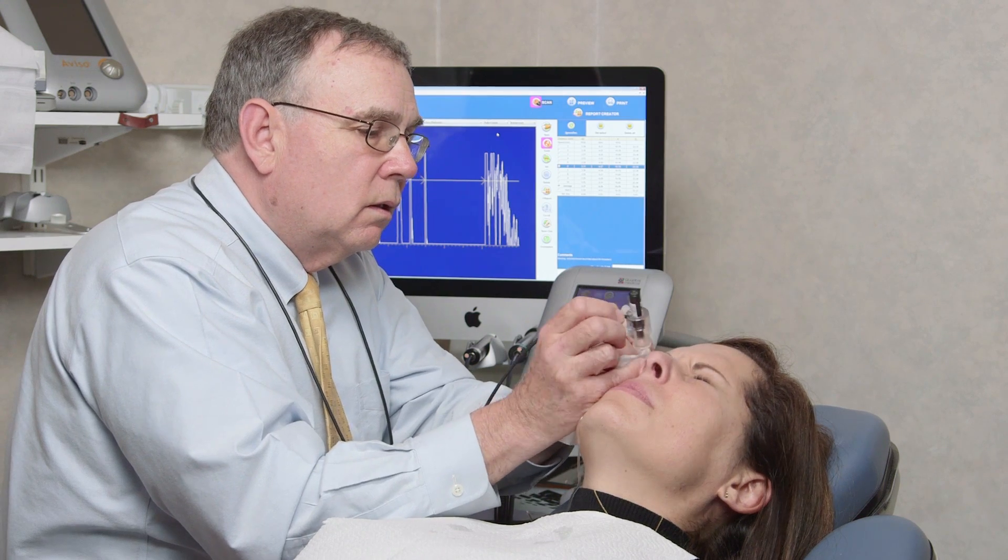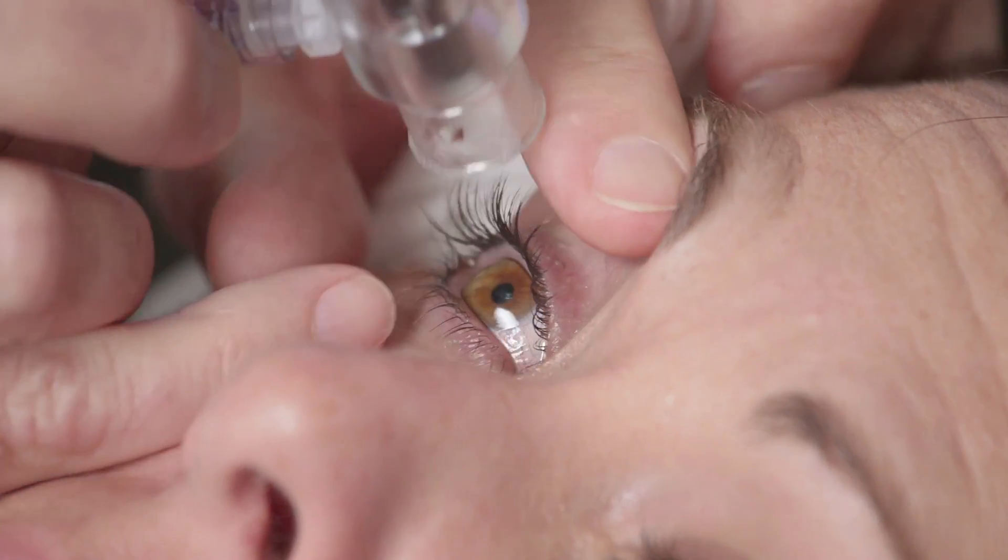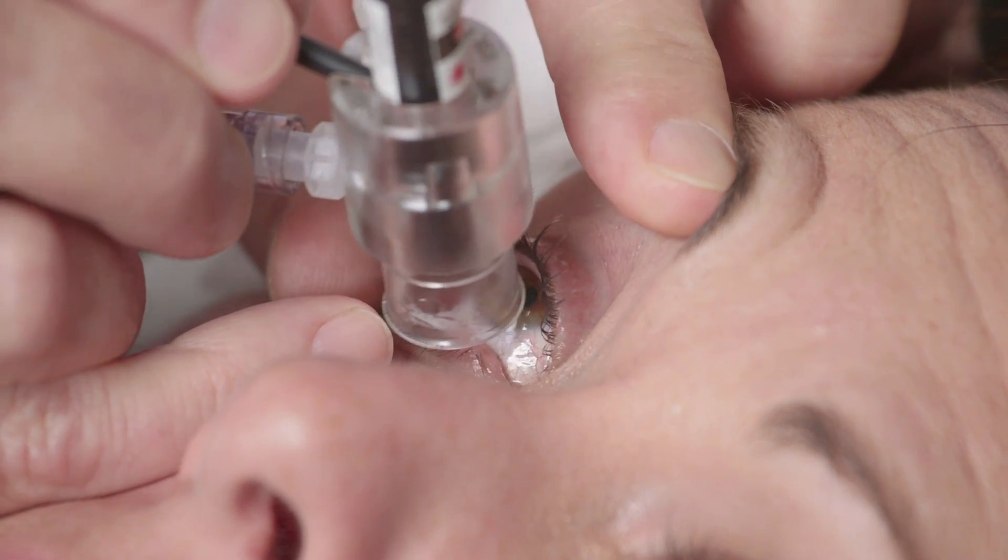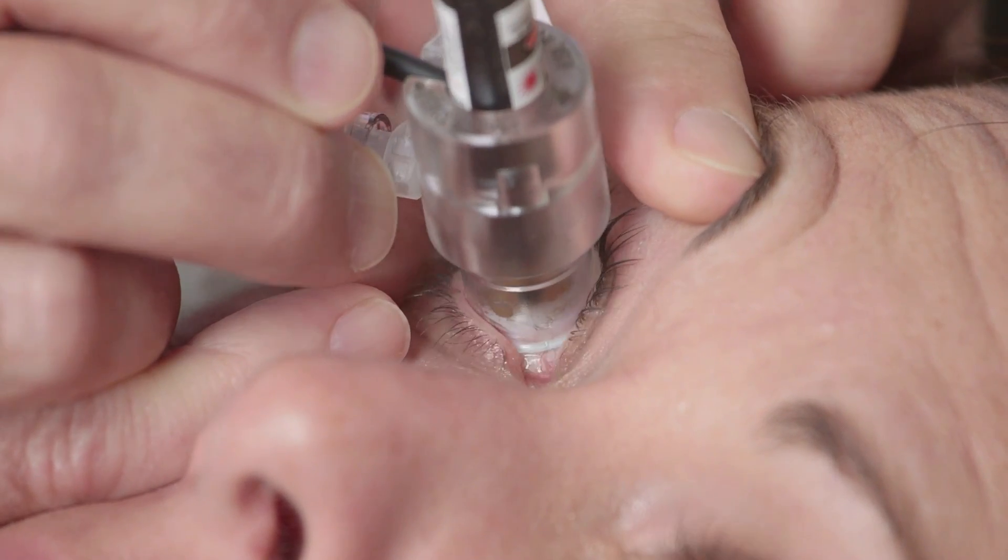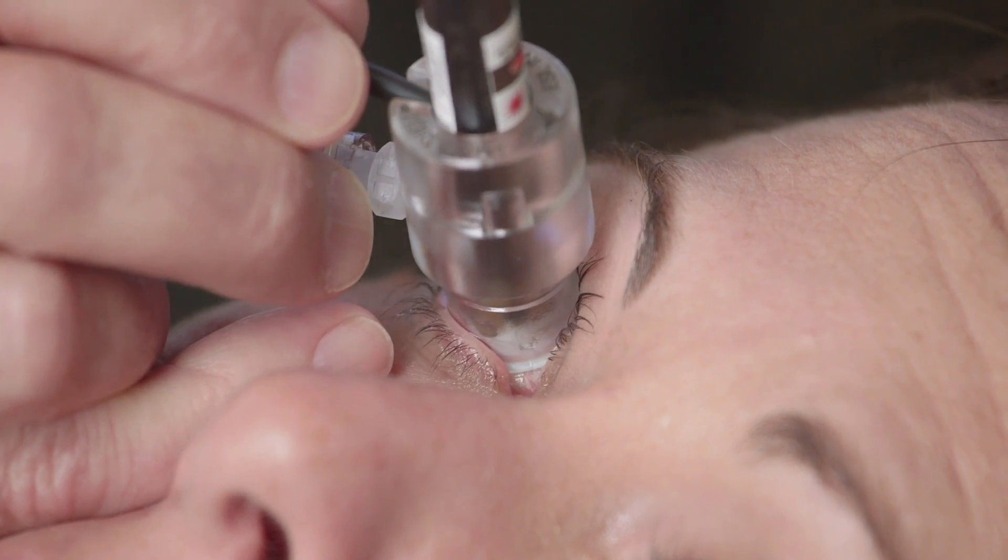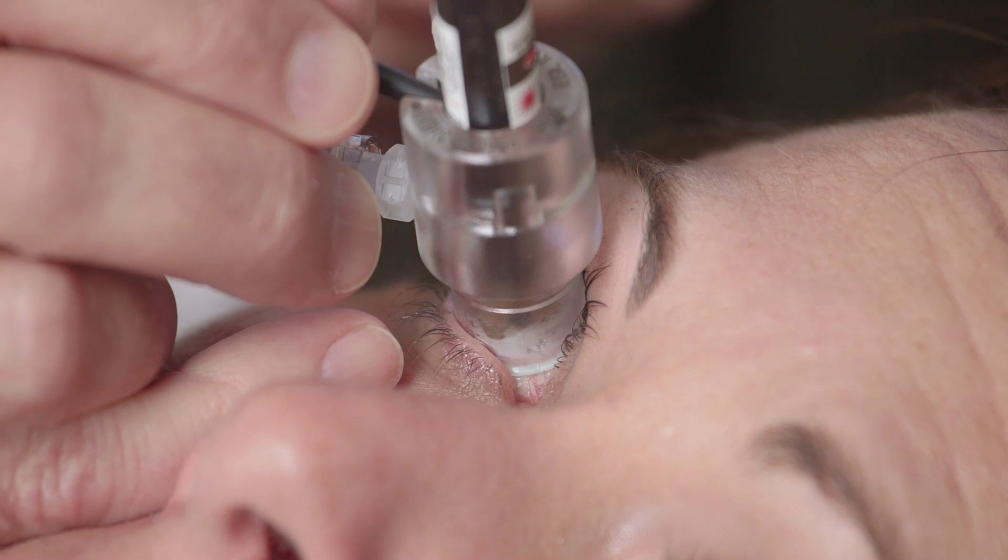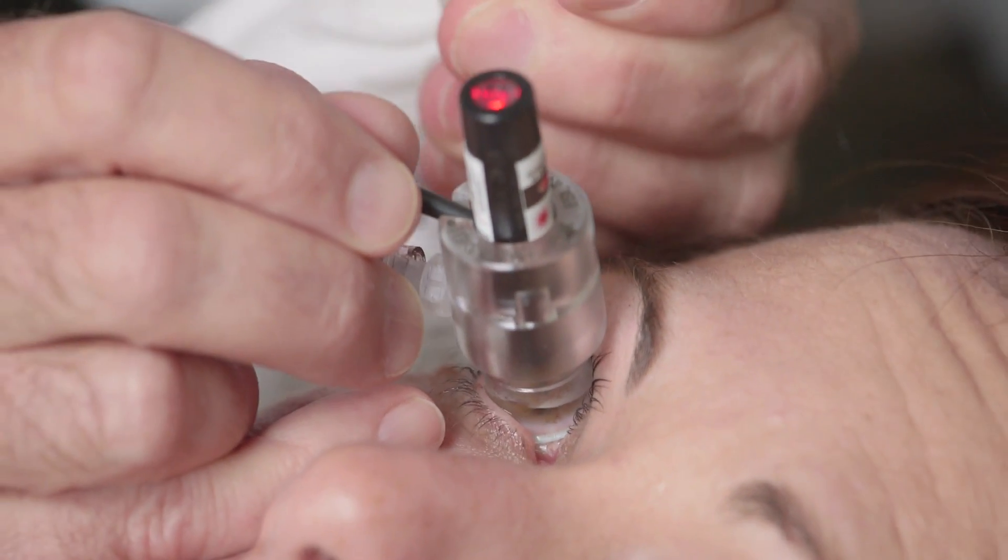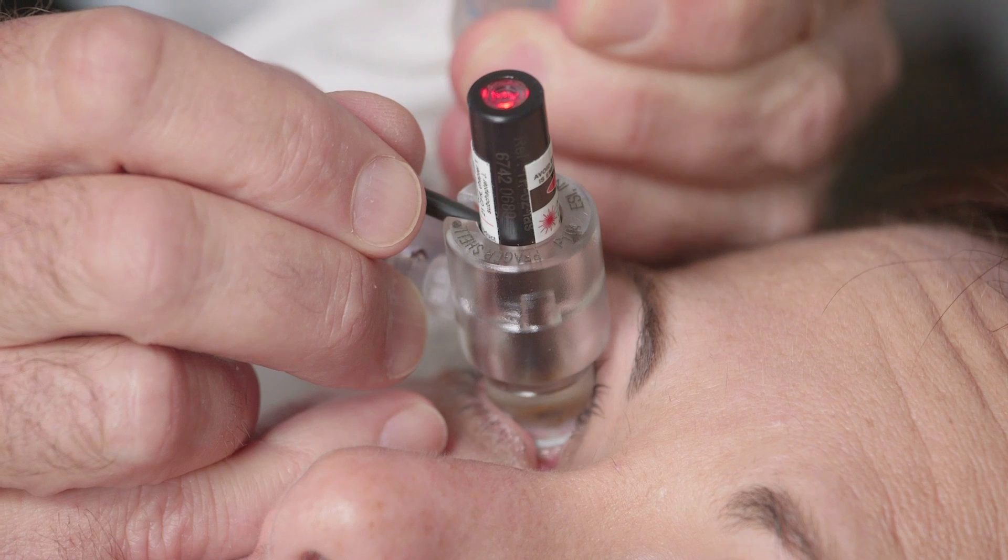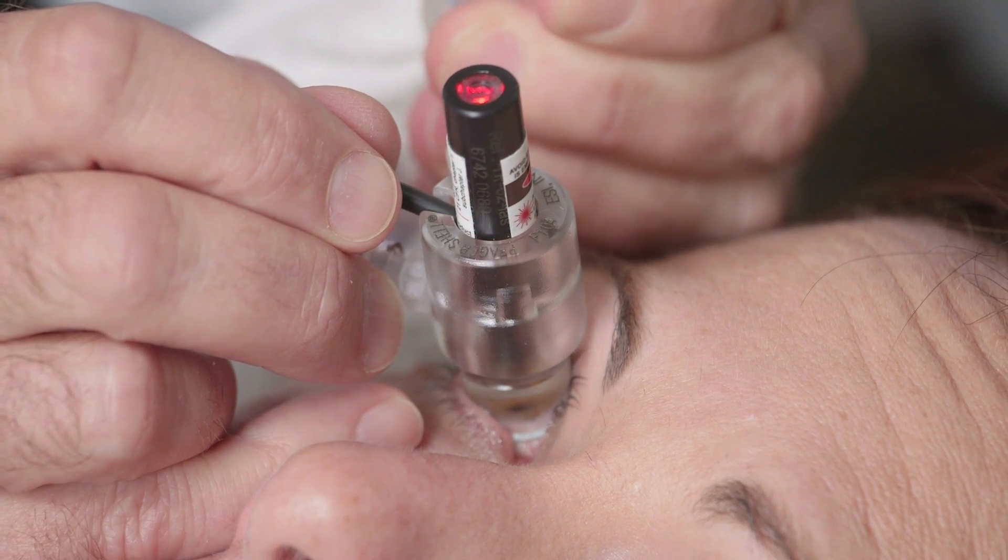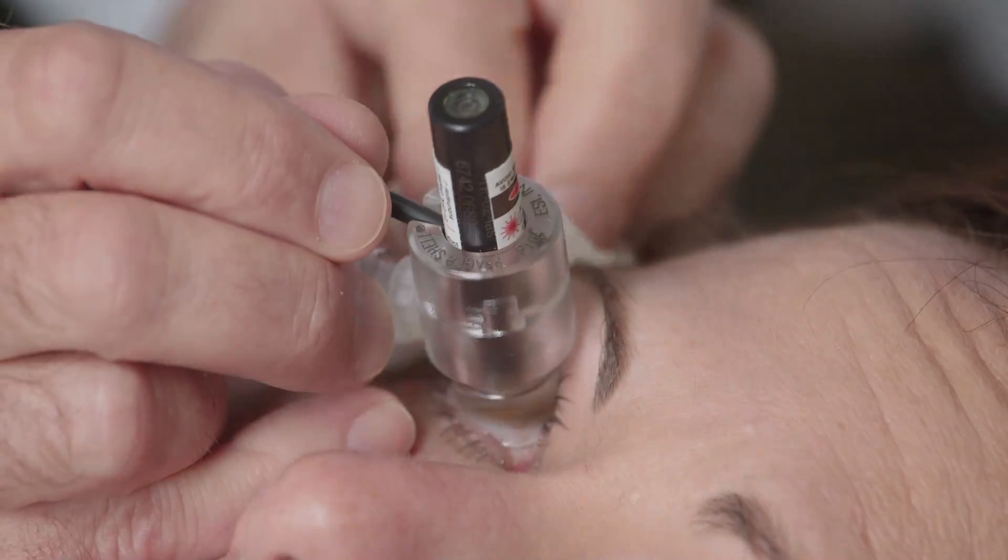Scleral shells come in different sizes that correspond with a range of corneal diameters. The Prager shell, seen here, is only one of many brands of scleral shells. This particular shell comes in one size only. The Prager shell is fitted with single-use disposable tubing for infusion of fluid from the side via a plunger. The shell itself must be disinfected between patients and the tubing discarded and replaced. For other shells, the coupling medium must be poured into the top of the shell with one hand, while the other hand stabilizes the shell on the eye. Each examiner should find the method that works best for them.